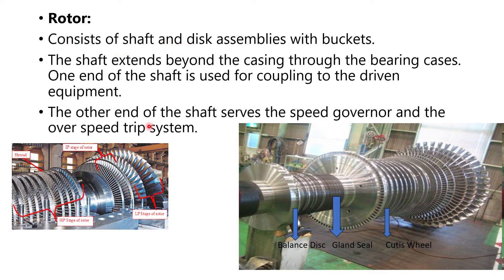This is the exhaust duct from where the steam passes towards the condenser. The rotor consists of: the rotor itself, the thrust collar, the gland sealing arrangement, the Curtis wheel, and the rotor blades. The rotor shaft on both sides extends beyond the casing to support the bearings. The rotor blades are secured together on the top by shrouds to reduce vibration and blade damage. On the left hand side is the HP stage and on the right is the LP stage of the rotor.